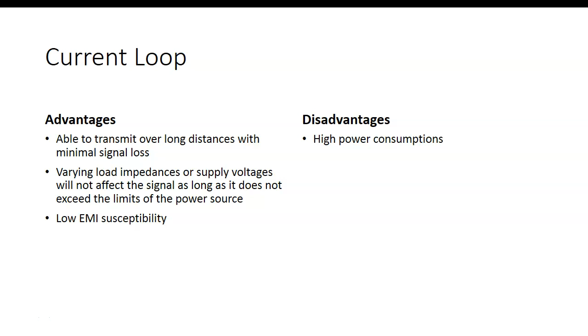So this is basically a current loop: we have a power source, and then we have a sensor. If the current tries to go up, the power supply automatically adjusts itself. If the current tries to go down from what it's supposed to be, it automatically compensates. So we can ignore the resistance of the wire, because the power supply is going to try to output 4 to 20 milliamps. That means we can send these signals a long way.